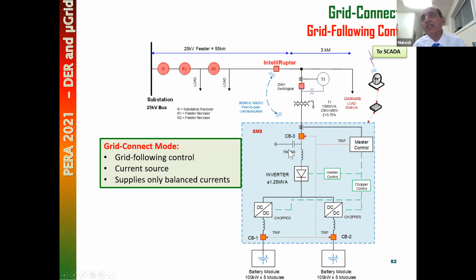Grid following mode means this is a current source, basically doing two things: charging a battery or helping to shave the peak load. It only supplies balanced three-phase current. Very important point: in grid following mode, it supplies only a balanced three-phase current. That's how this inverter is designed. This inverter does not supply unbalanced current in the grid mode. In grid following mode, all the unbalanced current comes from the feeder.